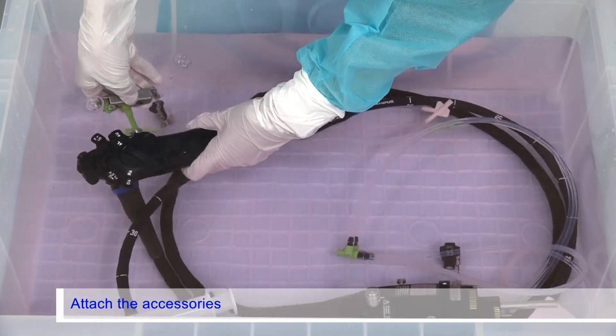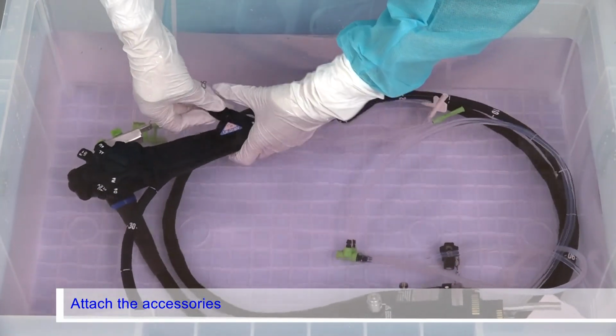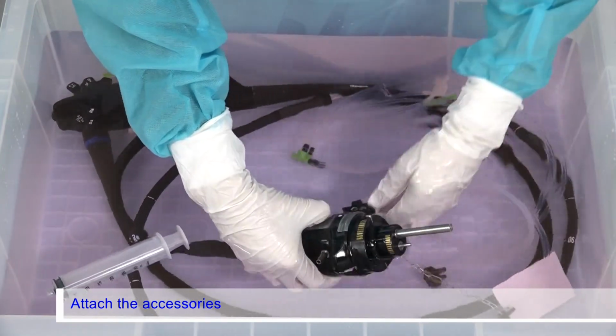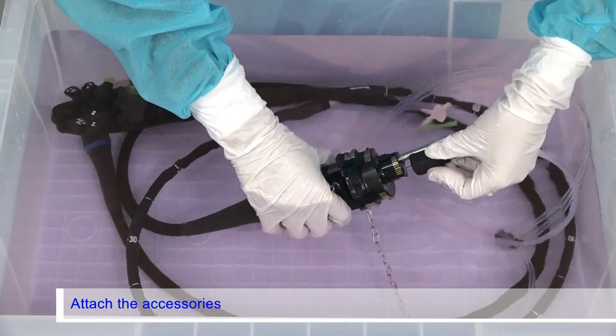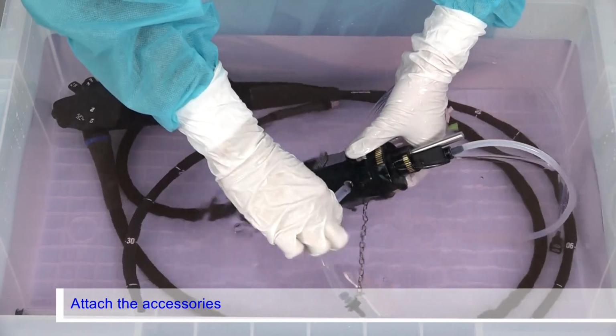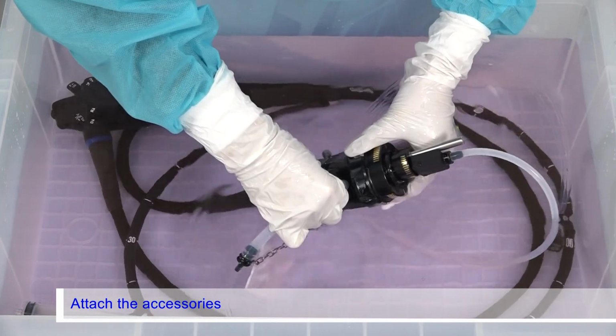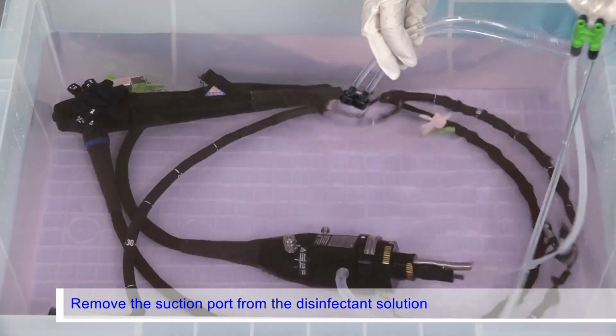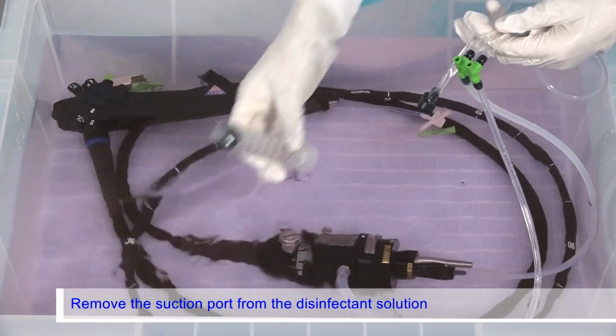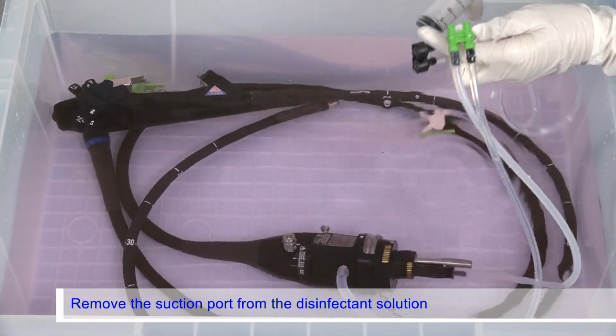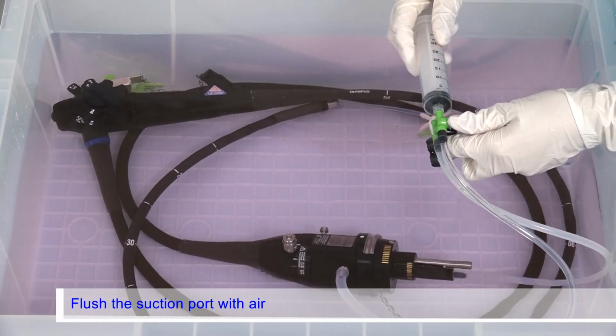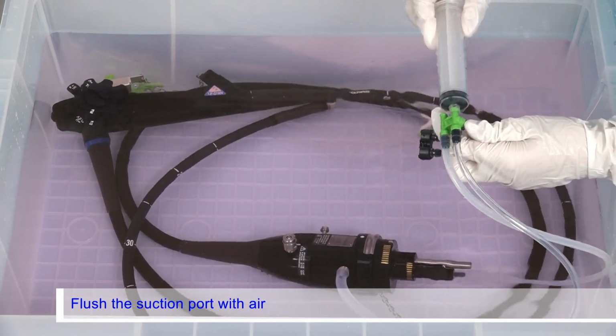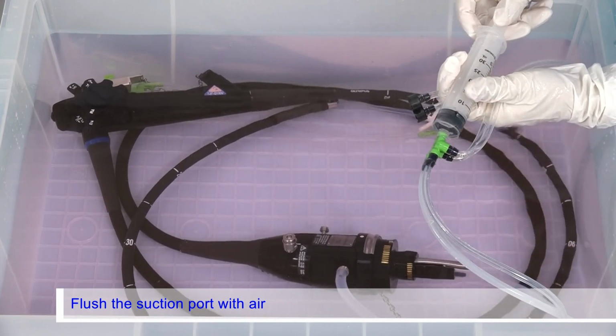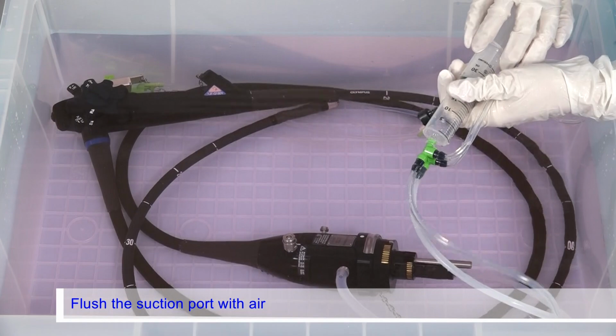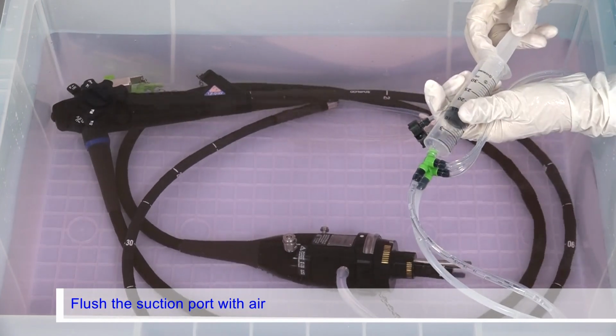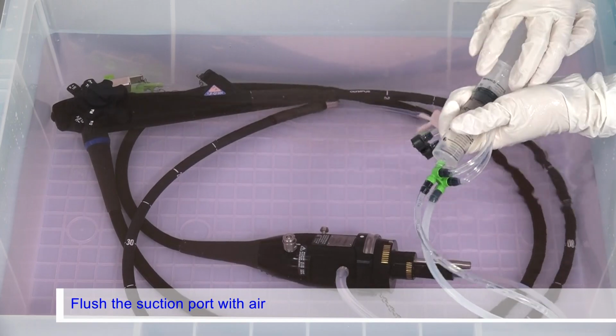Attach the channel plug and the injection tube to the endoscope. Remove the suction port of the injection tube from the disinfectant solution. Attach a sterile 30 milliliter syringe to the suction channel port of the injection tube and pull the syringe plunger to fill the syringe with air. Then push in the plunger to flush the suction channel with 90 milliliters of air.